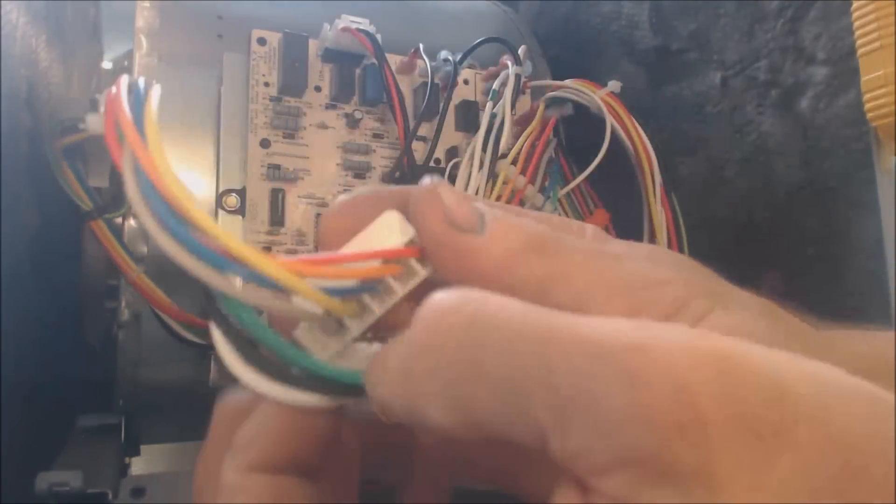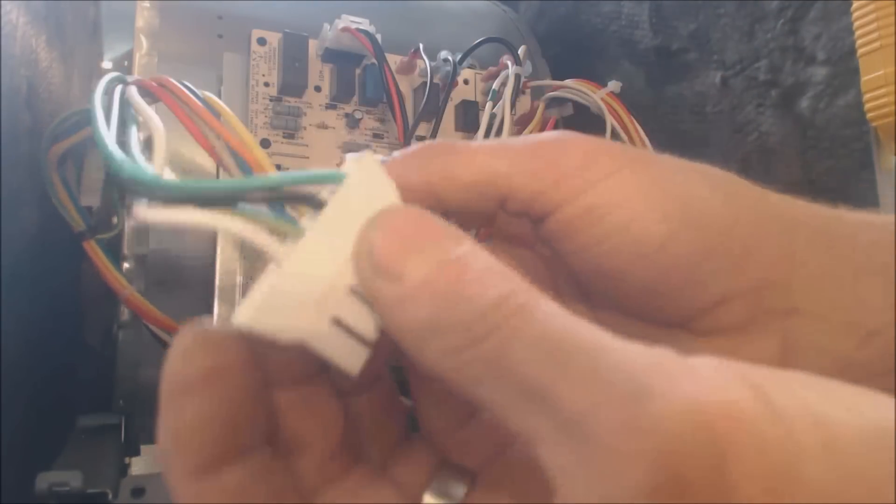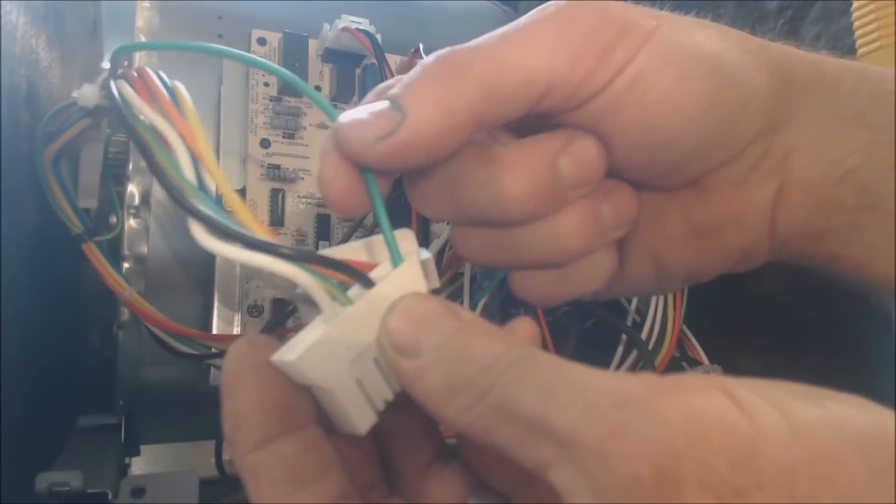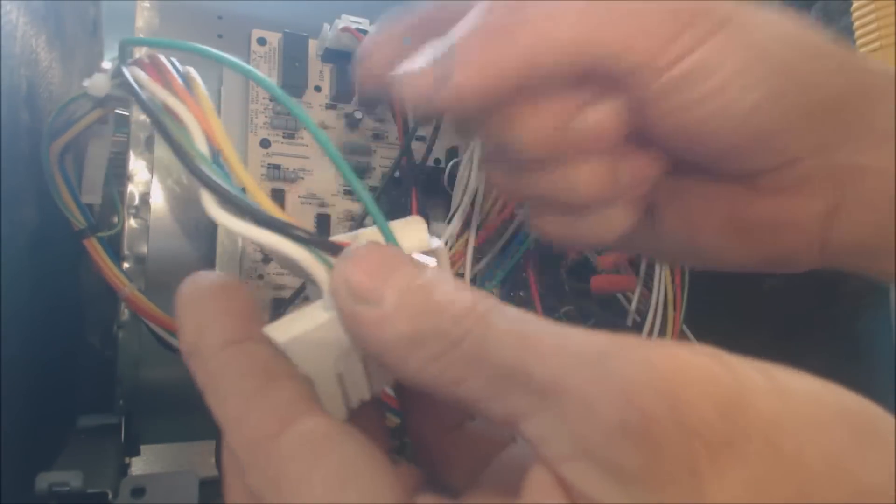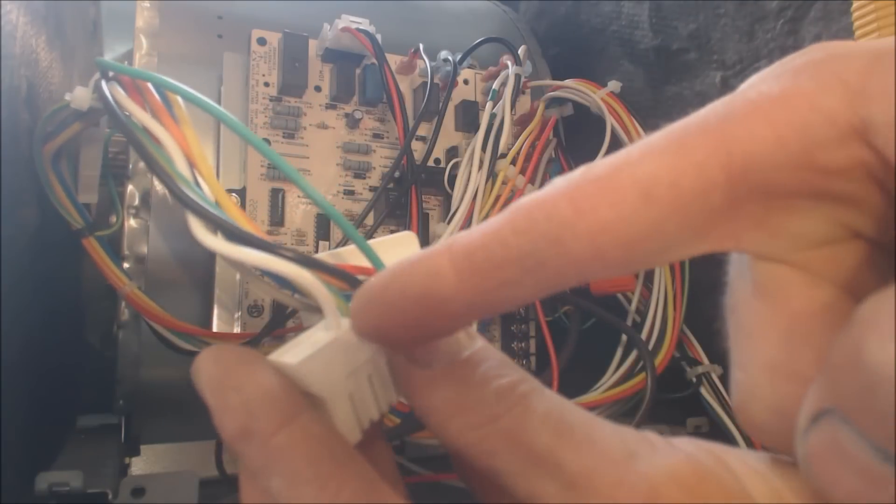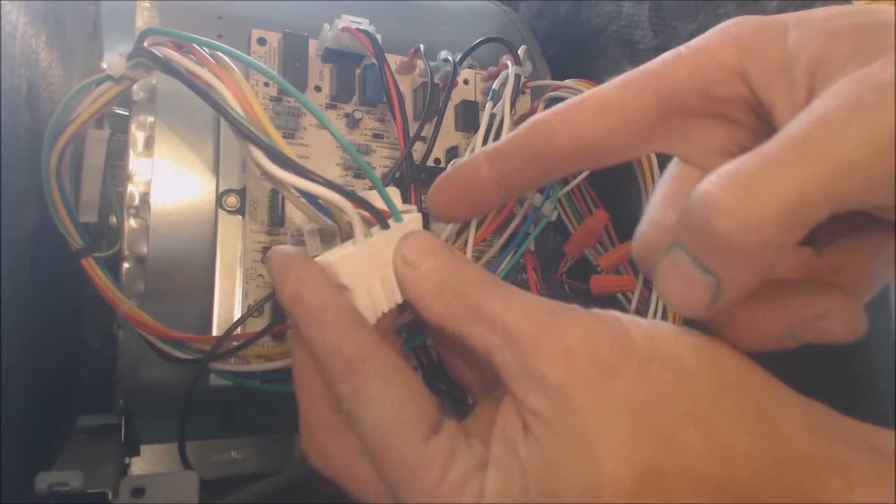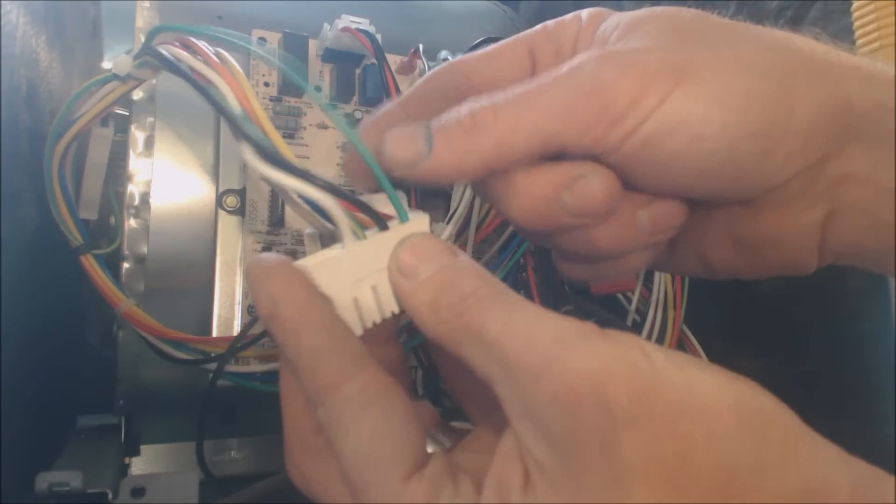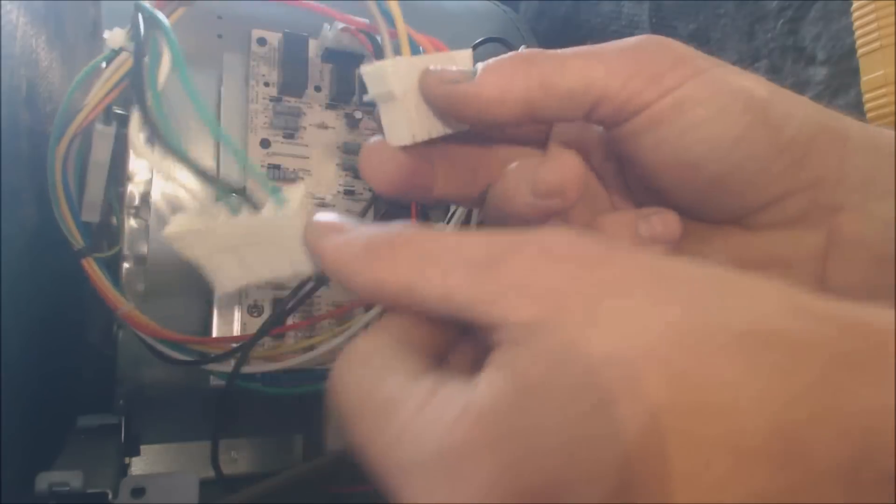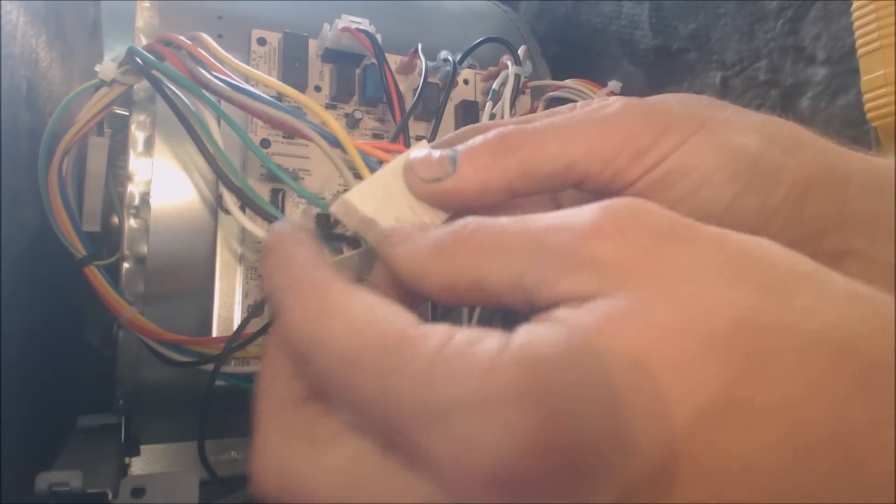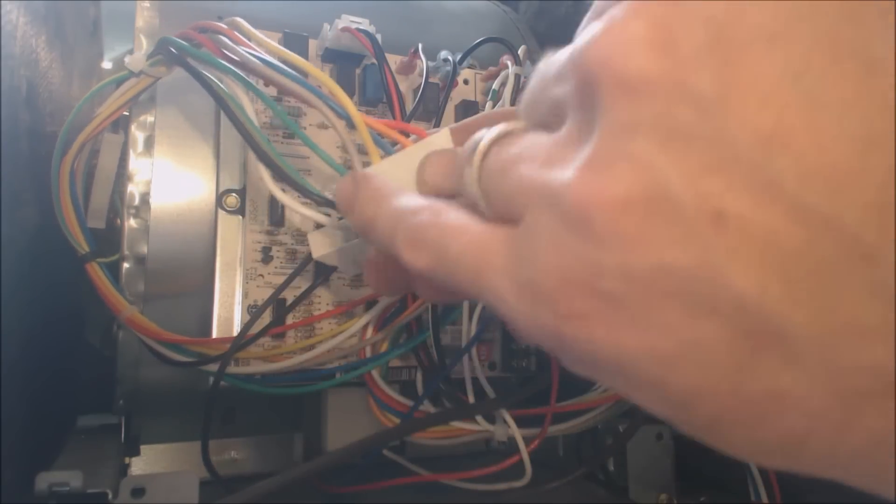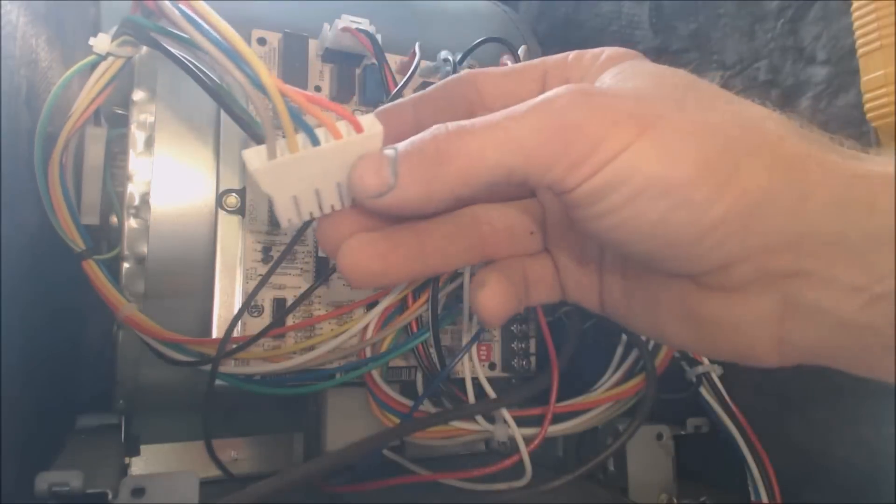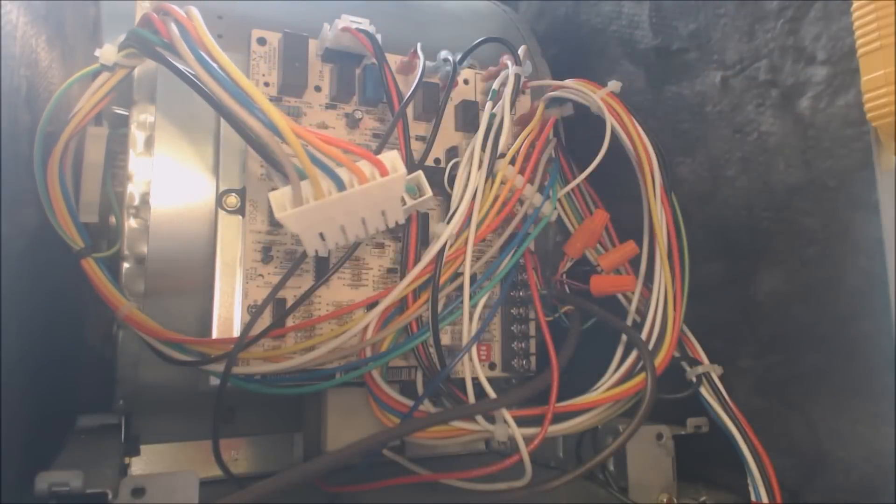So you have your high voltage side right here and your common for your low voltage. So that's your hot, your common and your ground. And then this is your common for your 24 volt side. These are your five speeds right here. Okay, depending on whatever the manufacturer has programmed.